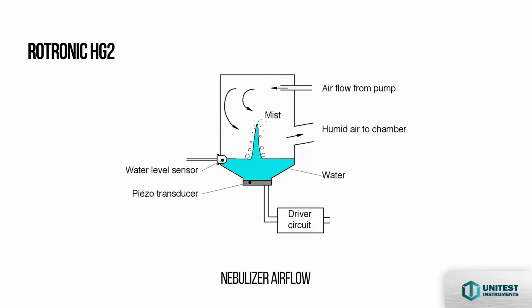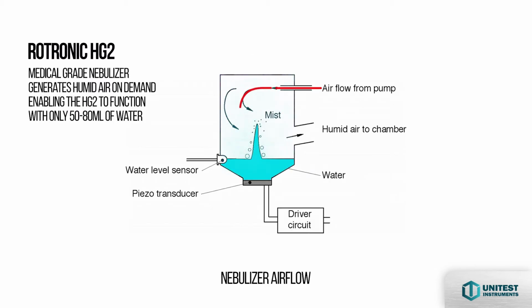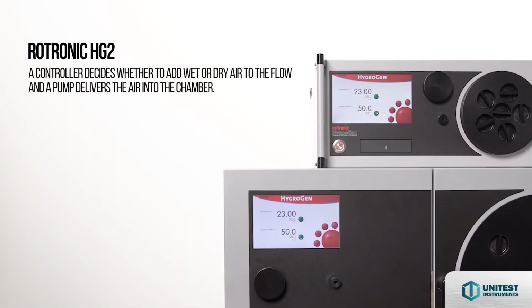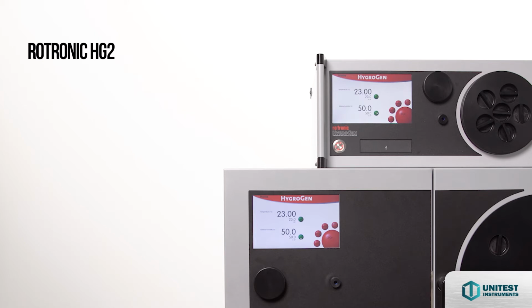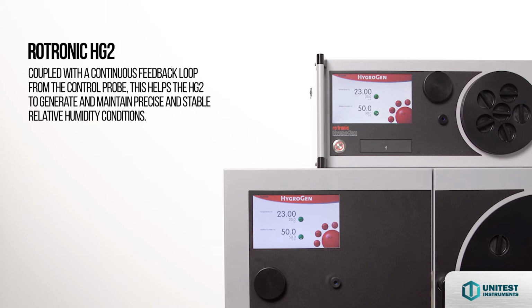A medical-grade nebulizer that generates humid air on demand enables the HG2 to function with only 50 to 80 milliliters of water in the reservoir, making the setup simple. A controller then decides whether to add wet or dry air to the flow, and a pump delivers the air into the chamber. Coupled with a continuous feedback loop from the control probe, this helps the HG2 to generate and maintain precise and stable relative humidity conditions.